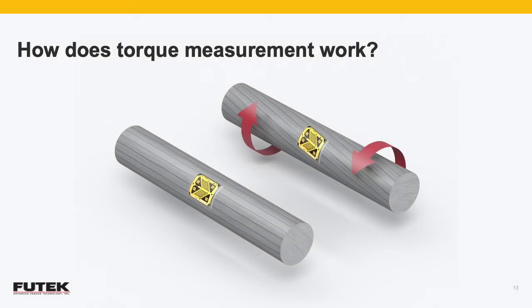Now we have spent time talking about the importance of torque measurement and application environments, but let's actually look at the products. All of our torque solutions utilize strain gauges in a Wheatstone bridge configuration to convert torque input into differential voltage output. Strain gauges are resistors that are bonded onto the flexural component of the torque sensor, and the deformation of the flexural component results in deformation of the strain gauge, which causes the resistance of the strain gauge to change. Such a signal can be converted and standardized using FUTEK signal conditioning electronics to provide analog or high-resolution digital output, for example SPI or USB, to allow communication with industrial control systems or personal computers.